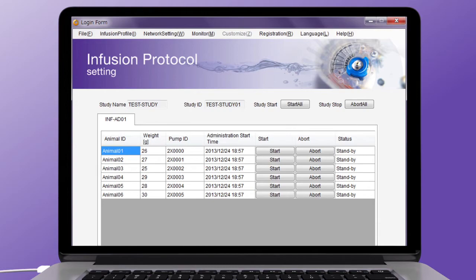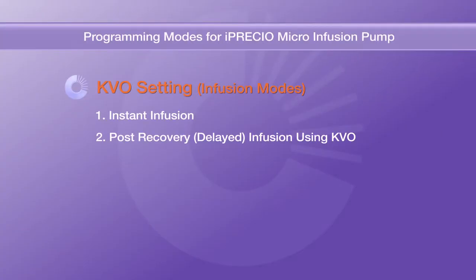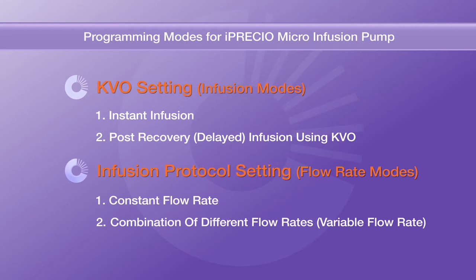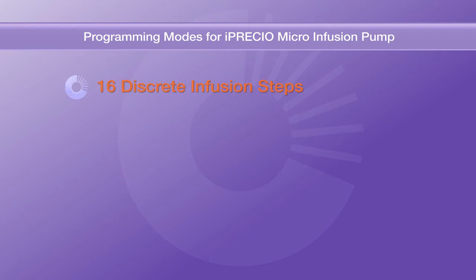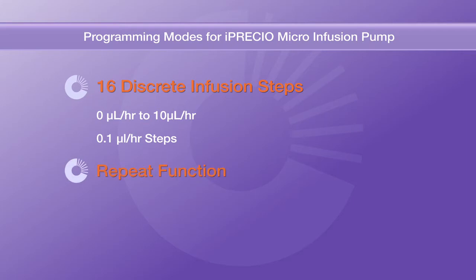and reprogramming wirelessly. The Windows-based management software allows the programming of a variety of infusion protocols with KVO setting and infusion protocol setting. You can start infusion instantly or after the animal has recovered from surgery. Also, you can configure up to 16 discrete infusion steps between 0 microliters per hour and 10 microliters per hour in 0.1 microliter per hour steps.